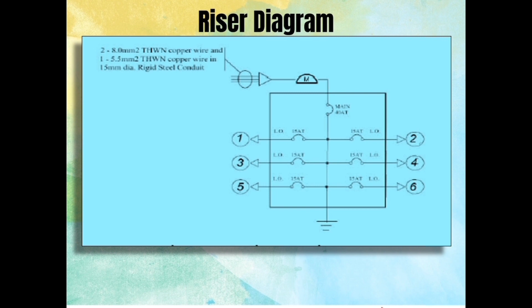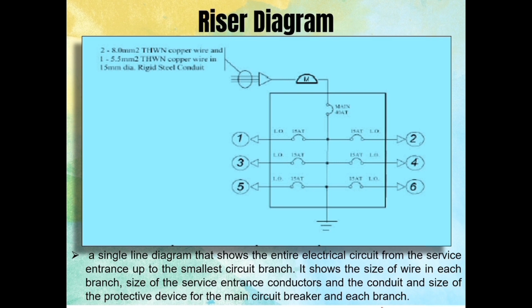Another example of riser diagram is a single line diagram, but it has 6 branches of lighting outlets. A riser diagram is a single line diagram that shows the entire electrical circuit from the service entrance up to the smallest circuit branch. It shows the size of wire in each branch, size of the service entrance conductors, the conduit, and size of the protective device from the main circuit breaker and each branch.